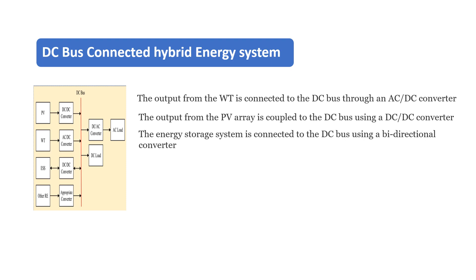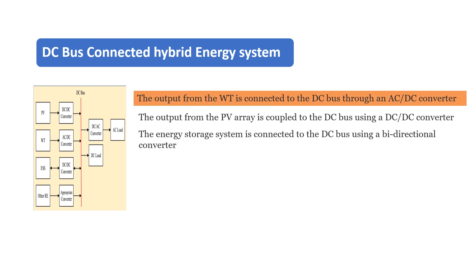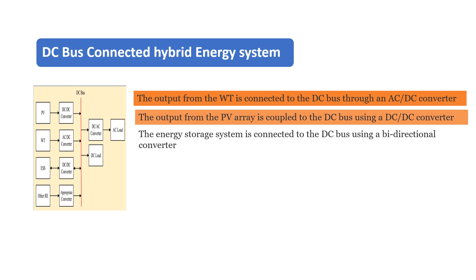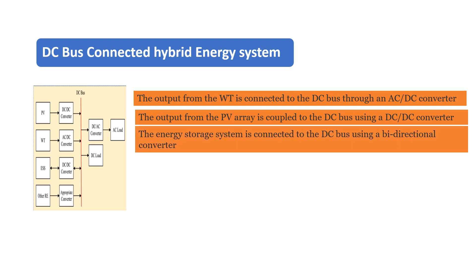In DC bus connected architecture, the output from the wind turbine is connected to the DC bus through an AC-DC converter, while the output from the PV array is coupled to the DC bus using a DC-DC converter. The energy storage system is connected to the DC bus using a bi-directional converter to allow its charging and discharging mechanism.